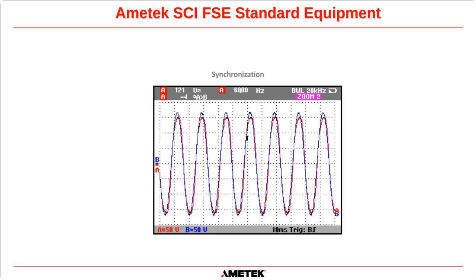There are things that can, I suppose, go wrong when you change all of the printed circuit boards within a system. It's very complex electronics that are involved. So if you want absolute reliability, then yes, it's absolutely recommended that you do an AC load test after a PM10 PCBR has been performed. It just gives you that warm and fuzzy feeling that the system is going to perform as designed. It should do. The way that our PCBR changeouts are designed, especially if it's done by one of our service engineers, is it shouldn't have any issues.